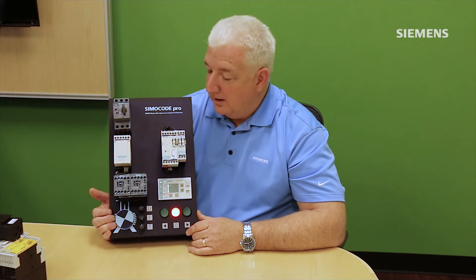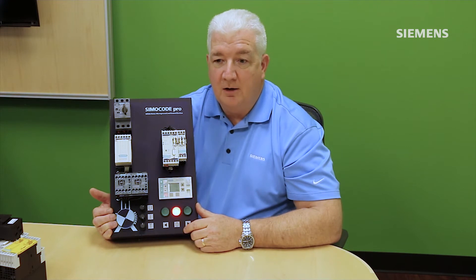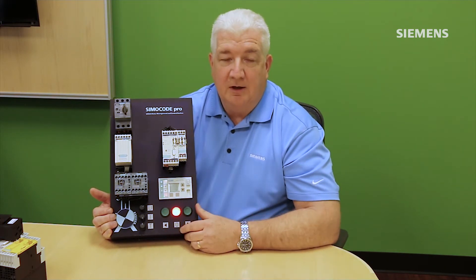Another available profile is the direct starter profile, where all control functions for starting and stopping the motor run through SIMOCODE. A local push button wires directly to the SIMOCODE rather than a parallel start-stop circuit, and a start command over the network also comes into SIMOCODE. This is similar to starting your car — turning the key doesn't send voltage directly to the starter; it sends a signal to your car's computer, and you may also have a key fob as an alternative start method.